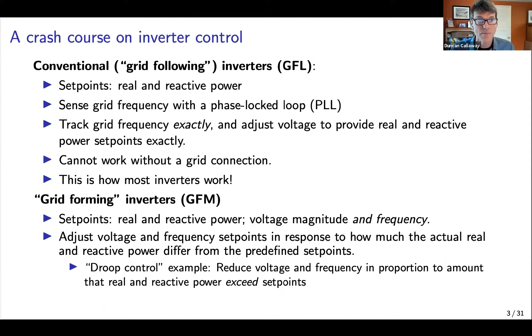So if I put the grid following and grid forming converters head to head, if we compare what they can do, a grid following converter, which is what most of our devices are today, will instantaneously control real and reactive power and can basically guard themselves against fault currents. However, they cannot operate standalone, and you could never have a 100% grid following converter-based grid. Whereas a grid forming converter, on the other hand, instantaneously will balance loads without a centralized coordination. That is, they power share if you have many of them together. They can operate standalone, and they can achieve a 100% penetration grid.